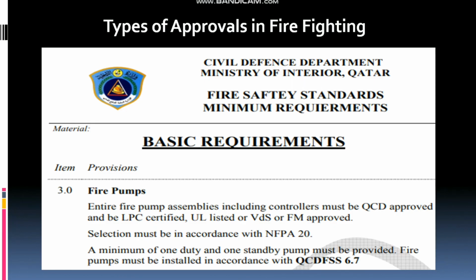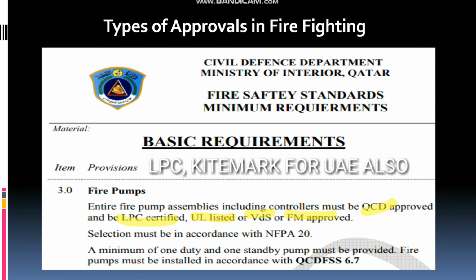What you see here is the Qatar Civil Defense fire pumps basic requirement. As per that, you can see there are multiple options. First, the fire pump assembly must be with the controller, QCD, that means Qatar Civil Defense approved, and after that there should be LPC certified, UL listed, or VDS or FM certified. So there are four different third party or organization listings that are approved in the Qatar Civil Defense.